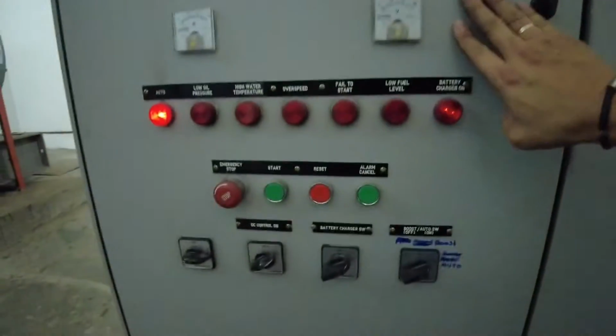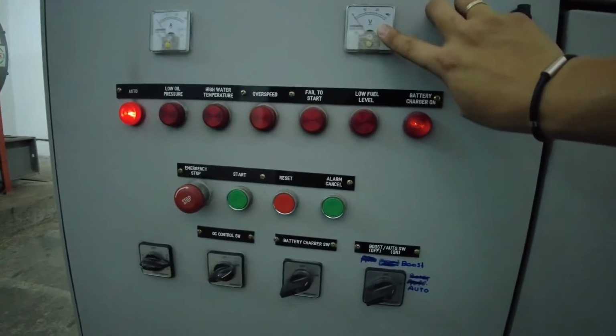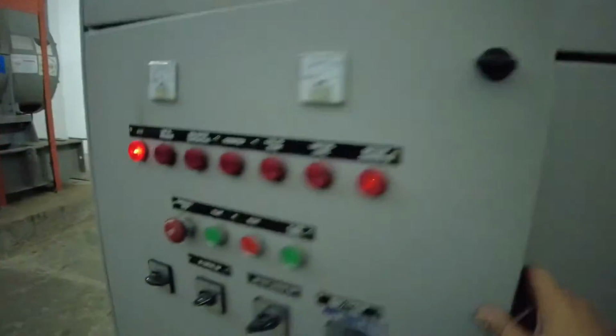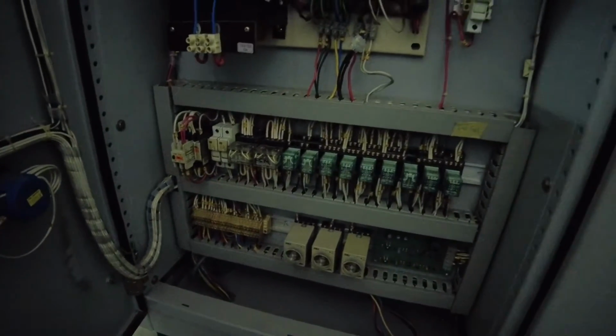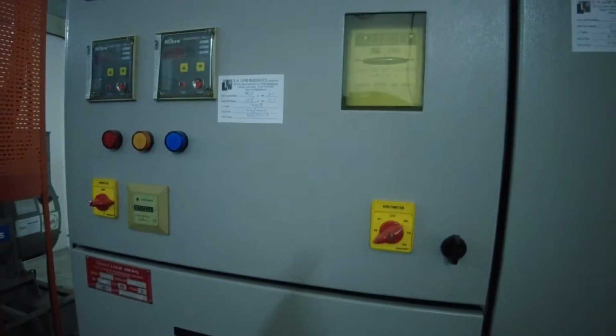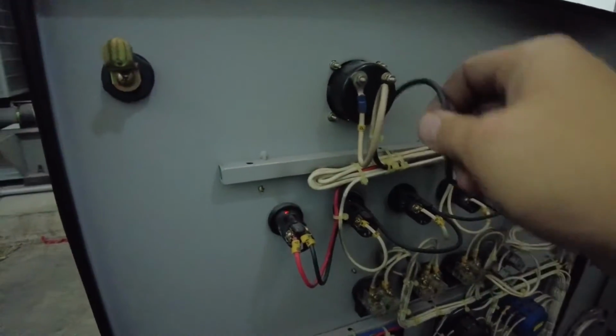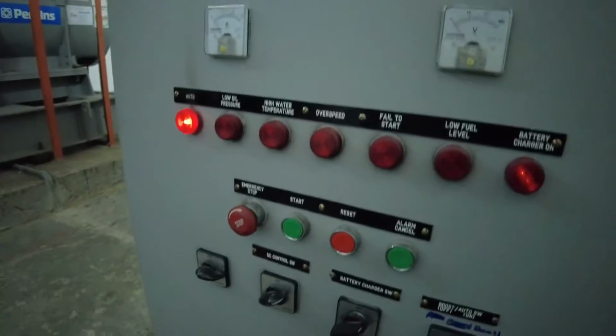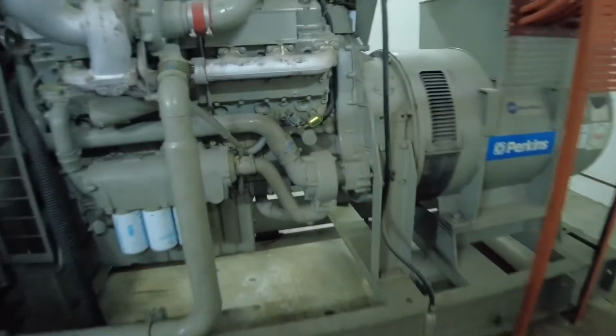After we check the radiator water level, we'll come back to this panel. Let's check the battery voltage. Oh, battery voltage is down. I don't think it can start. So need to troubleshoot what the problem is. The reason there's no voltage is because this voltmeter is faulty, so it's disconnected already. But after using a voltmeter to measure from the battery side, it's actually 29 volt DC available. So without further delay, we will just test run the genset by simulating the signal from ATS panel.